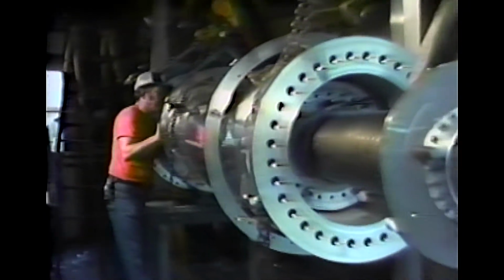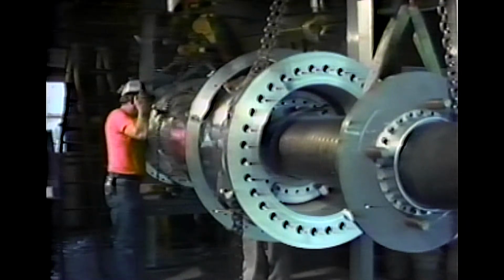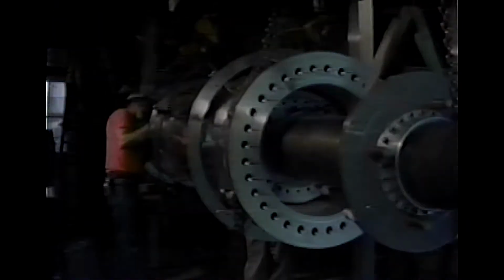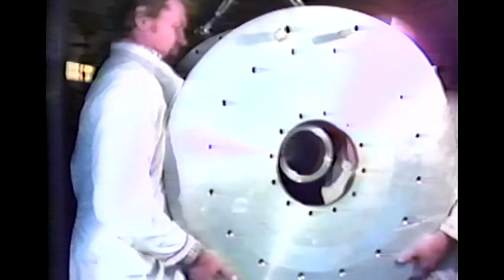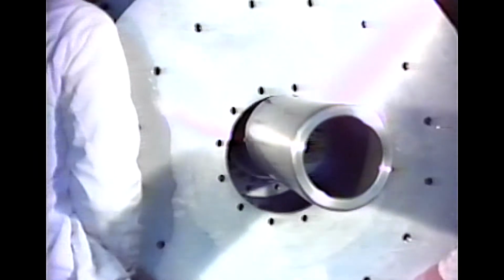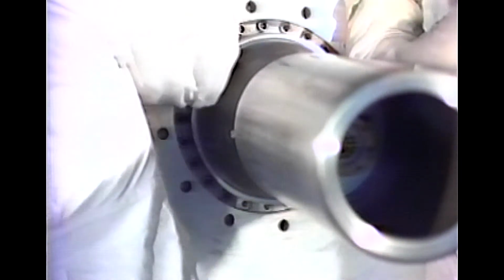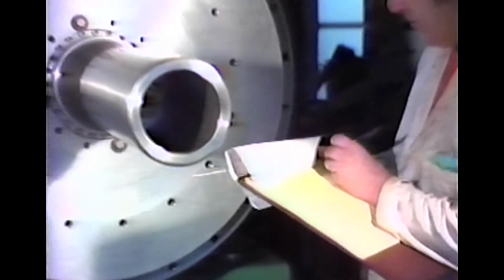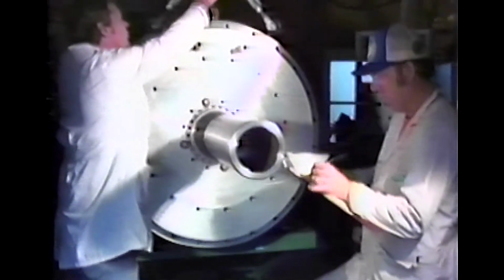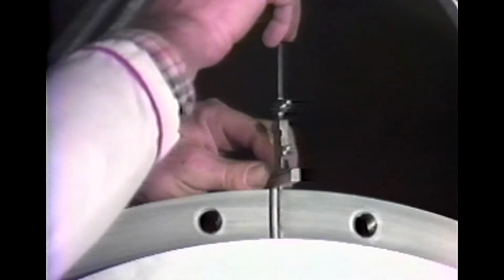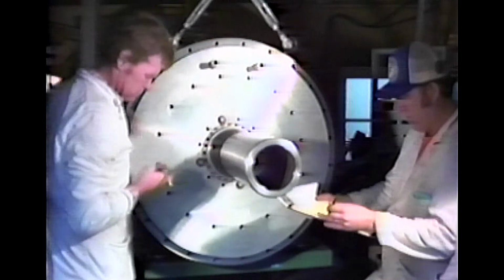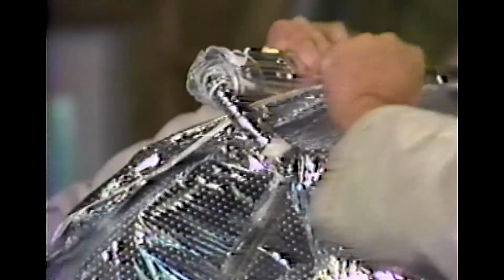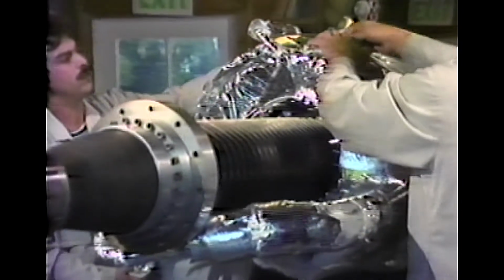With insulation in place and everything leak tight, the termination needs only the outer vacuum tank to complete the cryogenic section of the assembly. This portion of the termination is sealed by the flange, which makes the connection between the various high-pressure components of the termination and the vacuum containment vessel. Careful adjustment is necessary after assembly to ensure that the joints are vacuum tight. After a last check for leaks, more super insulation is added.